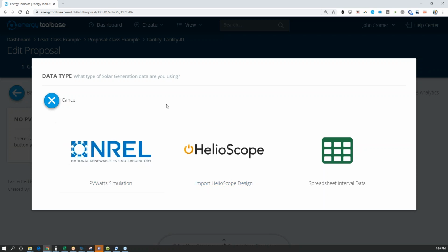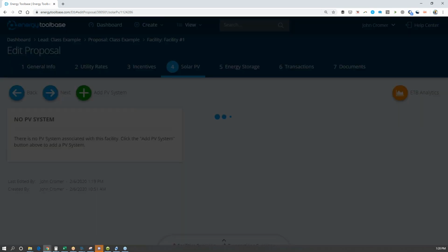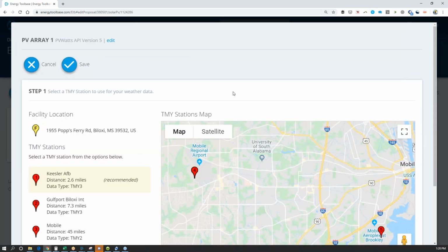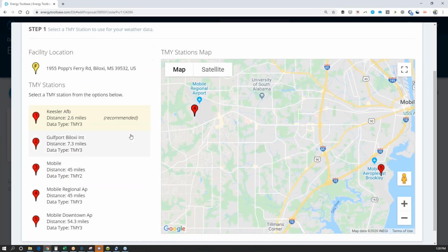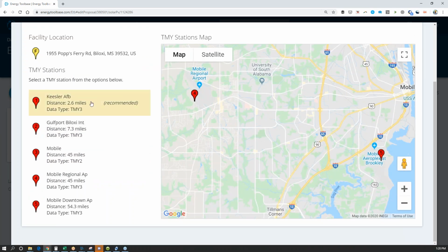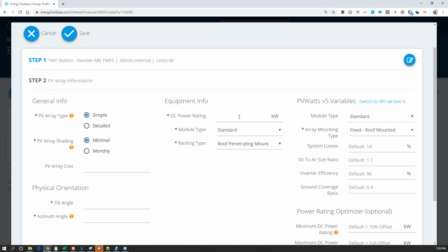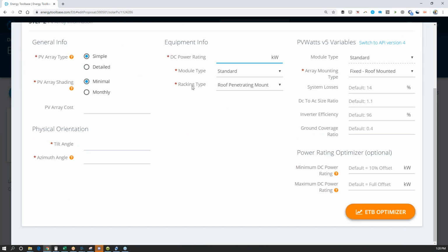And generally speaking, if you're staying 4 feet away from air conditioning equipment, and you're removing modules that are on little small subarray sections and only keeping nice, large, easy to install subarrays, you're not going to run into shading issues on commercial rooftops. And so for that reason, we can just enter our PVWatts data based on local weather data and just enter in our array size.